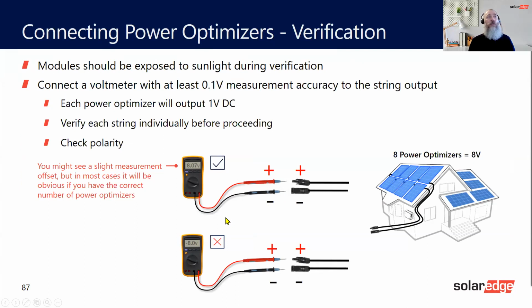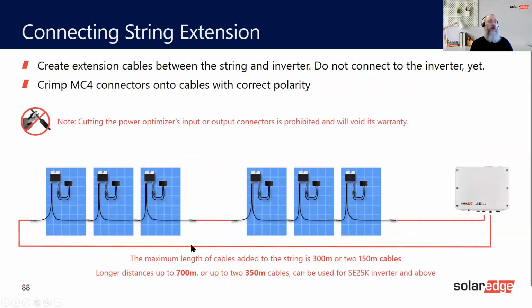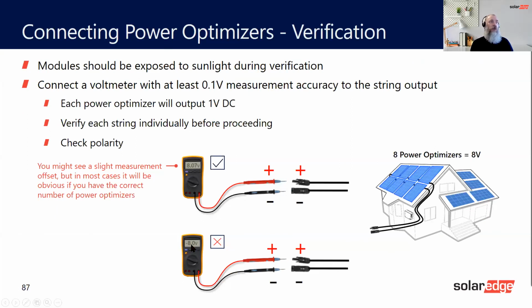Another thing is to make sure that you have the correct polarity. If you connect your test lead with the plus in the right one and the minus in the right one, and then connect it to the cable, you will get the correct polarity. If, however, you've got minus, it means that you have the polarity either on one of the cables here is incorrect or one of the cables up here is incorrect, and you're getting reverse polarity. The inverter will not start with reverse polarity. If you have a minus voltage on there, the inverter will not start, okay?